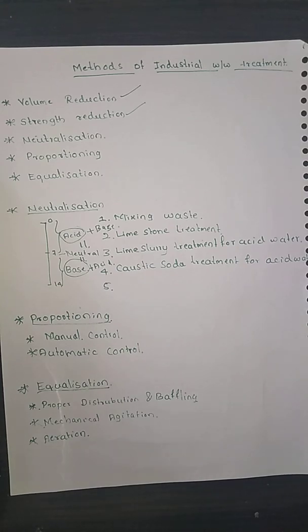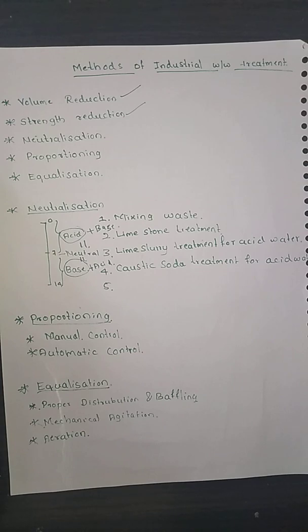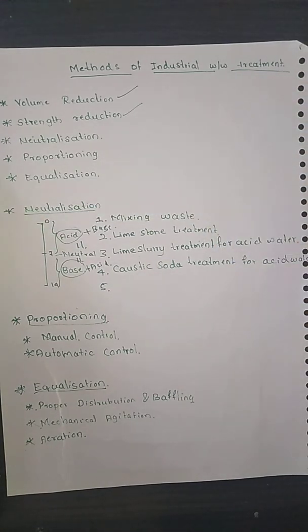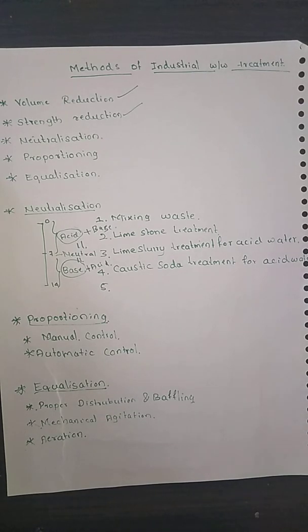Another method is lime slurry treatment, where the strength of the acids is reduced by adding lime slurry, since lime is basic in nature. There is also caustic soda treatment for acidic waste. In all these neutralization methods, the principle is the same: if the wastewater is acidic, we add bases; if it is basic, we add acids — reducing the ultimate effect of the acidic or basic solution.